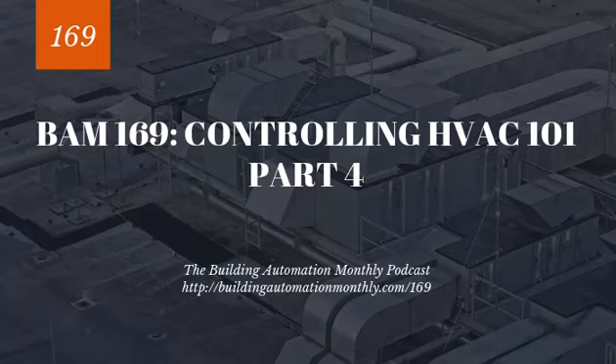Now, staging has a lot of nuances to it. You've got to get your timing right. You have to understand the impact of when you stage on and stage off multiple boilers. This can provide more efficient control in low load scenarios because you're able to really trim down your production of heat. Whereas with the Unison Control, you only have so much you can trim down that heat production.